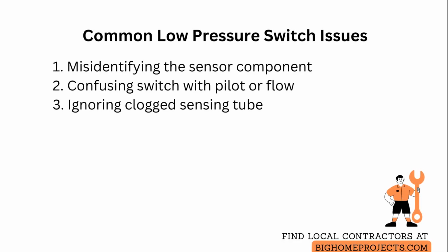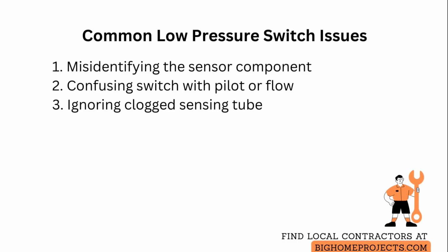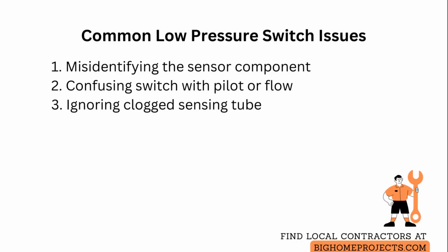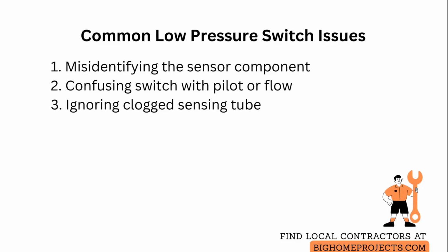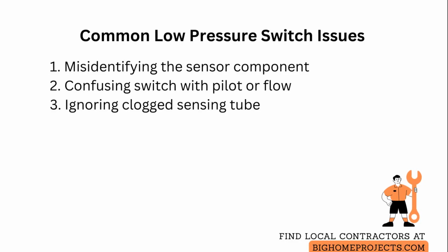Another issue is mistaking a pilot safety or flow switch for the low-pressure gas switch. Compare physical location near the gas valve and confirm whether it senses pressure in a tube or monitors flame or flow to avoid swapping unrelated components.